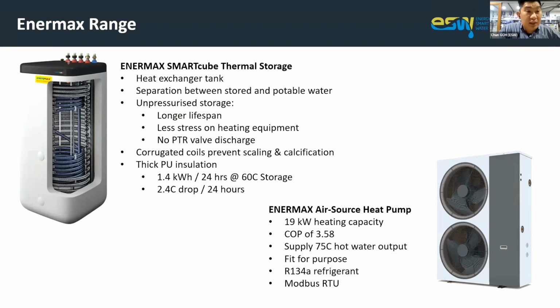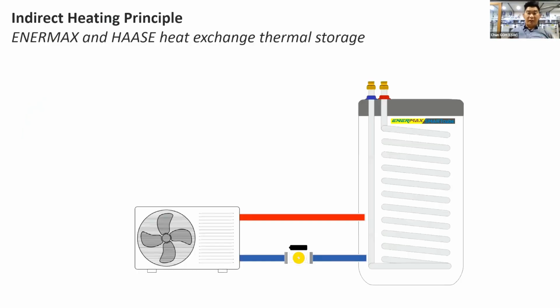As you can see on the slide here, that's the thermal storage that we have, which we call a thermal battery. We found that in a good heat pump system, the heat pump has to be one of the pieces of equipment able to produce a very good heat source. And then with the good heat source, you have to keep it, store it in the proper thermal storage, so that you can effectively and efficiently use the heat source you generated. Otherwise, if you don't have proper storage in the heat pump system, you're going to waste the heat that you generated. So it has to be a combined system that works it out.